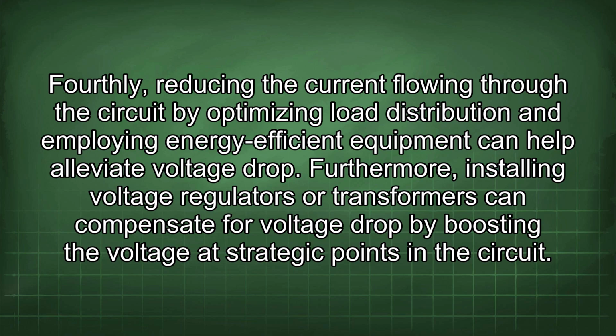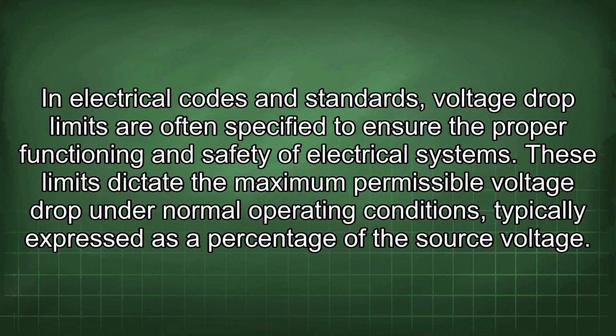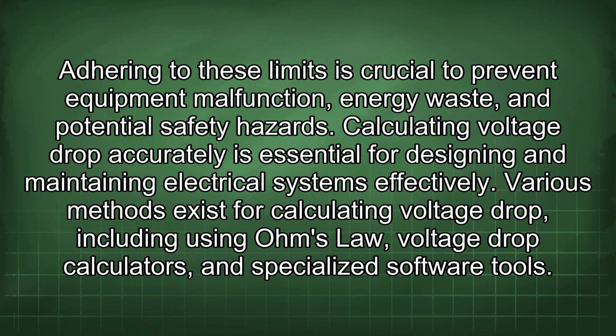Furthermore, installing voltage regulators or transformers can compensate for voltage drop by boosting the voltage at strategic points in the circuit. In electrical codes and standards, voltage drop limits are often specified to ensure the proper functioning and safety of electrical systems. These limits dictate the maximum permissible voltage drop under normal operating conditions, typically expressed as a percentage of the source voltage. Adhering to these limits is crucial to prevent equipment malfunction, energy waste, and potential safety hazards.